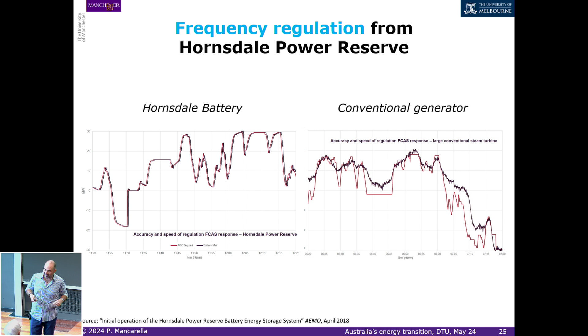So this is the frequency, and that's the droop response of the battery. A delay that cannot even be noticed, a perfect droop response. Now this has to be compared with a conventional generator that is taking 3 or 4 seconds to understand that something is happening in the grid. And the battery has already provided basically full droop response, stabilizing the grid and so on.